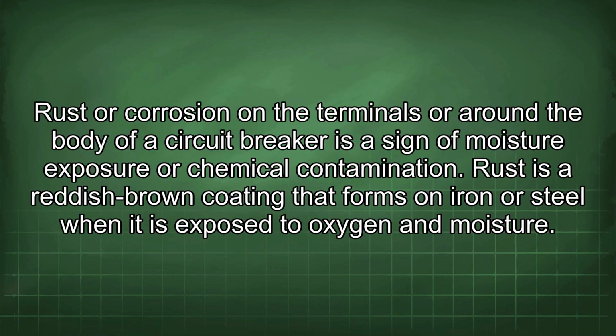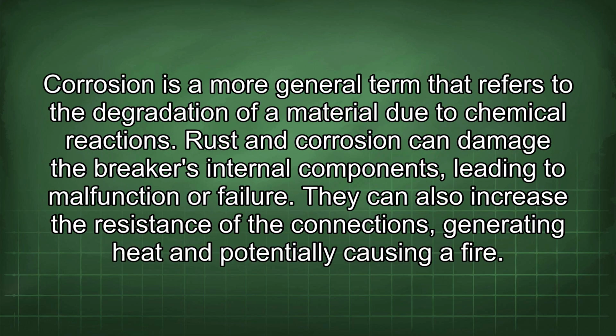Rust or corrosion on the terminals or around the body of a circuit breaker is a sign of moisture exposure or chemical contamination. Rust is a reddish-brown coating that forms on iron or steel when it is exposed to oxygen and moisture. Corrosion is a more general term that refers to the degradation of a material due to chemical reactions. Rust and corrosion can damage the breaker's internal components, leading to malfunction or failure. They can also increase the resistance of the connections, generating heat and potentially causing a fire.